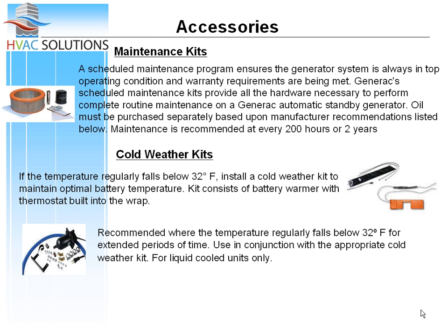All right, maintenance kits. We stock a full line of maintenance kits. I'm going to say right now we have them for the Honeywell line in total, and we are currently bringing in maintenance kits for the older Carrier Bryant, Generac units, that kind of thing. I'm going to say maintenance kits, there's not a whole lot to them. There's an air filter, some spark plugs. You're going to want to do these every 2 years or every 200 hours. I like to tell people to go out there every year, because even if you get just the slightest bit of runtime, you're going to want to change these out, because these actually use oil. Oh, and the oil is the other thing I forgot to tell you.